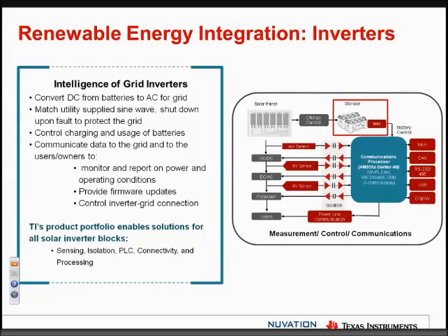So you've got a big battery, a bunch of DC energy that you've harvested and maybe stored in there. What do you do with it? Without an inverter, you can't make that accessible to the grid. The fundamental job of the inverter is to convert DC power to AC power. In a lot of applications we use what's called a bidirectional inverter, meaning it can go both ways: you can take AC power from the grid and charge your batteries, and take DC power from the battery side and supply it out to the grid.